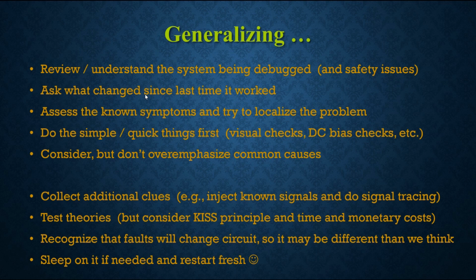Turns out our problem was, in some sense, a design problem. Sometimes you're troubleshooting a system that is well designed and has been debugged in advance and it just stopped working. In our case, we were taking a new engineering design and making it work better by finding some bugs in the design itself. Along the way, we did break it and then fix it. All right, so how do we fix it? We assess the known symptoms and we try to localize the problem. We knew which area of the whole radio we were messing with. So asking what changed since the last time it worked gave us the localization into the area of the circuitry that we should be looking at.